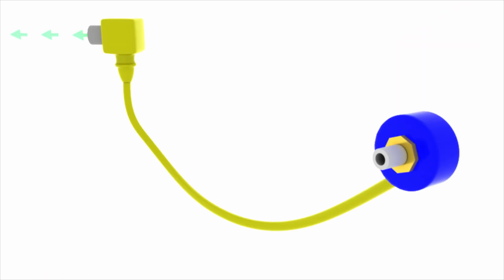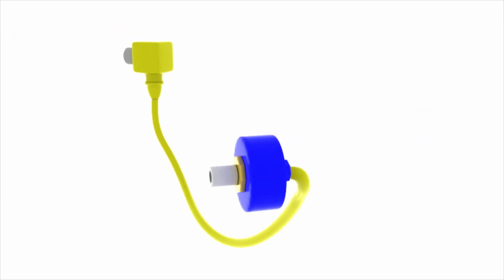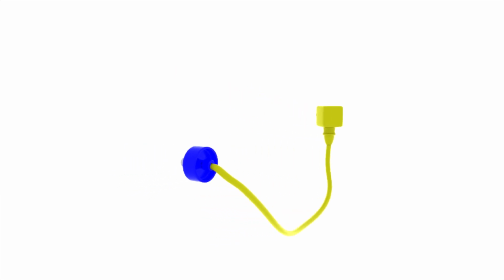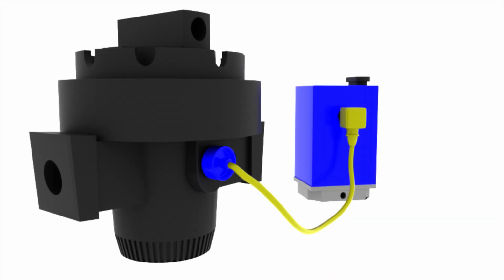Proportion Air's internal circuit board converts millivolt signal to voltage, 0 to 5, 1 to 5, 0 to 10 volts DC, or current signals, 4 to 20 milliamps. These larger signals are more resistant to electrical noise and are easier to send.